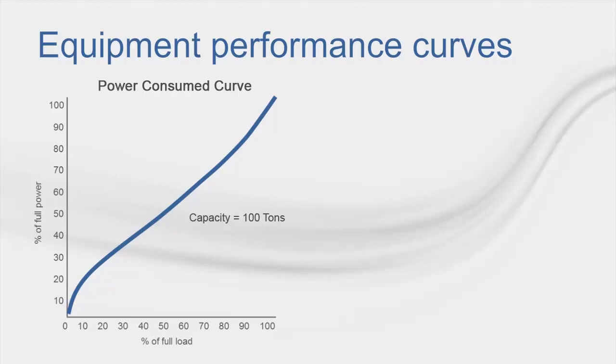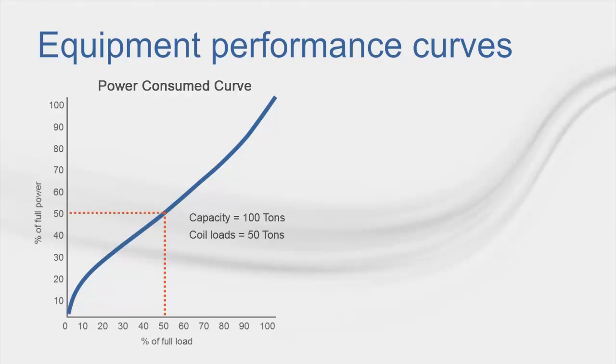Now, imagine that for the given hour, the coil loads assigned to the equipment total 50 tons. This is 50% of the design load for the equipment. We need to locate this point along the x-axis, then follow that line up to the curve. At this point, you would then follow the line to the left and see that the curve indicates that the power consumption for the compressor for the given hour would be 50% of the design value, or 50 kW.